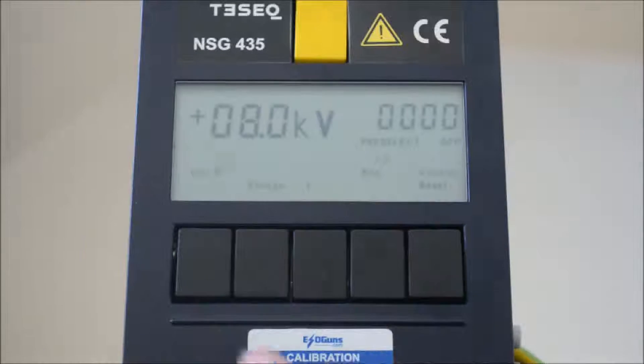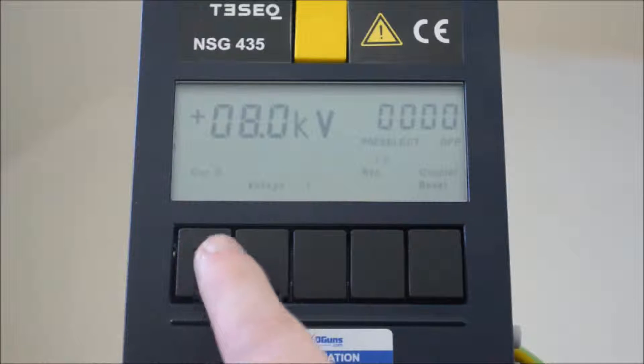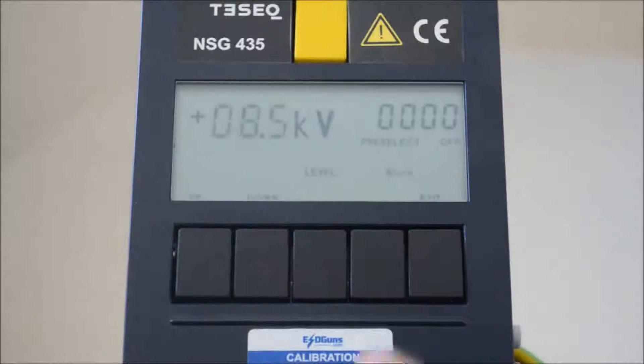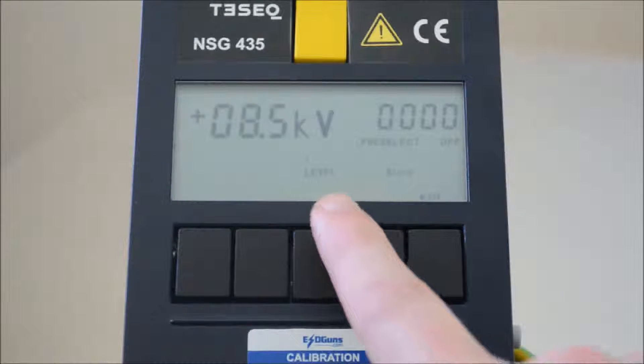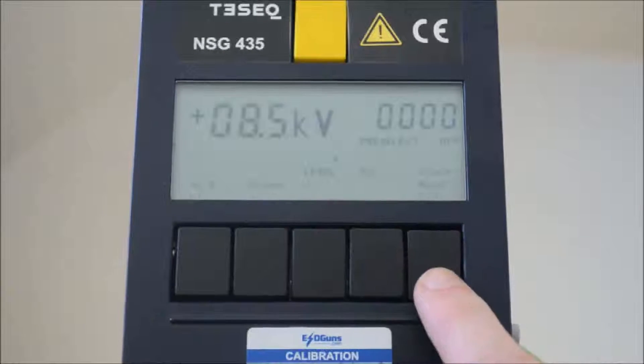Last but not least, let's save a test parameter for regular use. Air discharge for example, 8500 volts. Staying in the voltage menu we press F4 to store the setting. Using F3 we scroll through the pre-programmed IEC levels and select a memory location. We press F4 once again to assign the current value in the simulator to the IEC level 4 air discharge memory location.